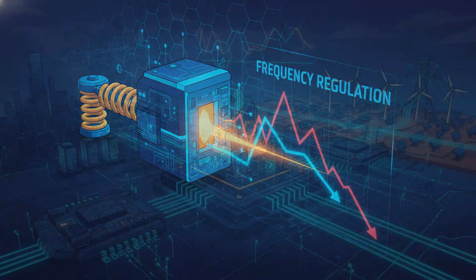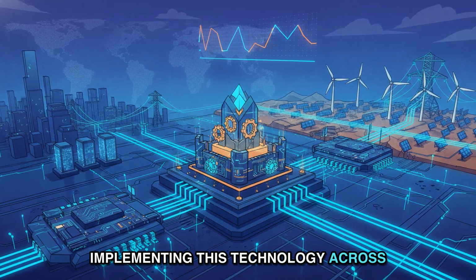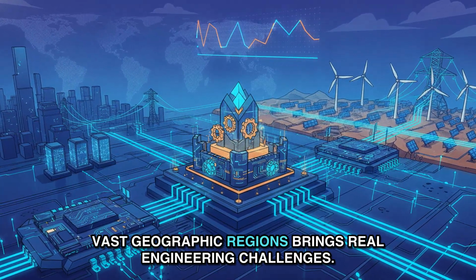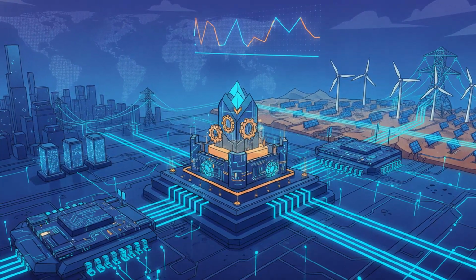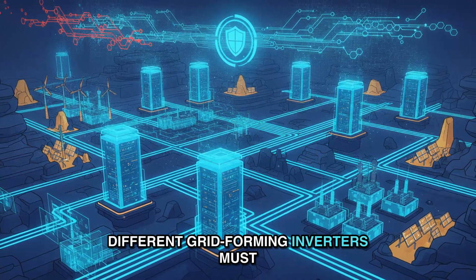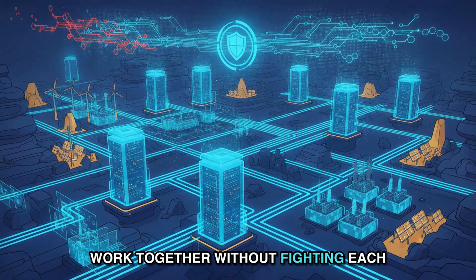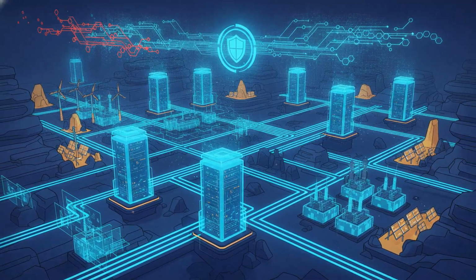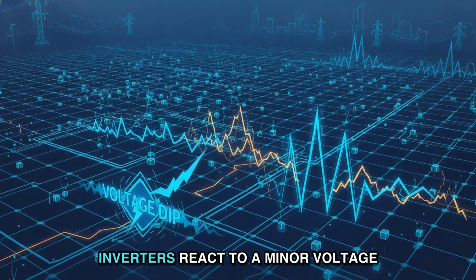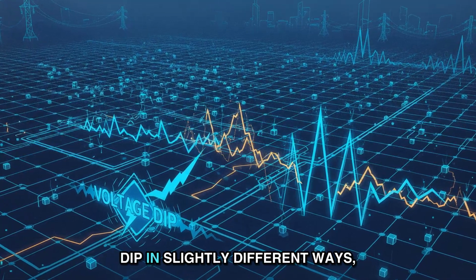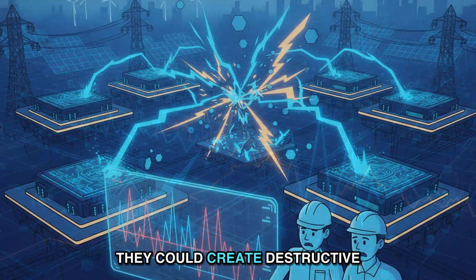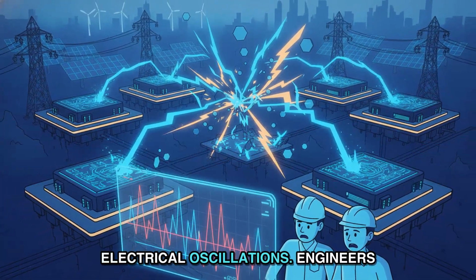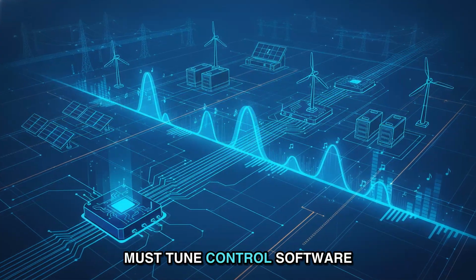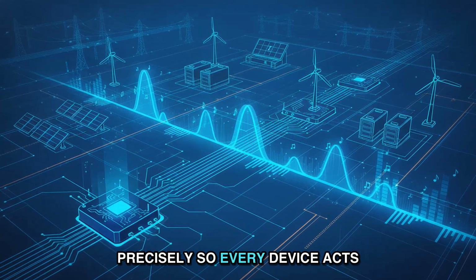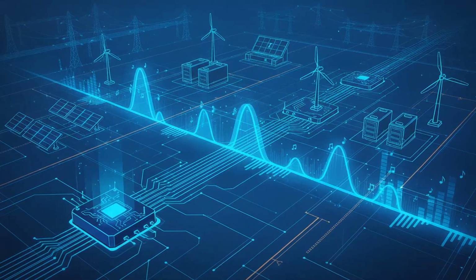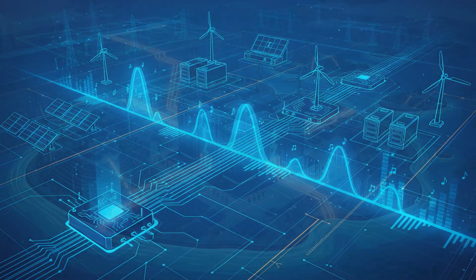Implementing this technology across vast geographic regions brings real engineering challenges. Different grid-forming inverters must work together without fighting each other across transmission lines. If thousands of scattered battery inverters react to a minor voltage dip in slightly different ways, they could create destructive electrical oscillations. Engineers must tune control software precisely so every device acts as part of a single, harmonious digital choir.